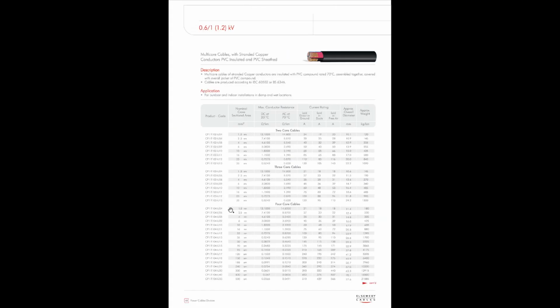So first we need a copper cable, 0.6/1.2 kilovolt. This one can withstand the 380 volt line-to-line voltage which we need. The second thing is how many cores we need. As the cable is supplying power to a three-phase load, a three-phase motor or a three-phase load with a neutral, we need three phases and a neutral. So we need a four-core cable. Okay, so let's zoom in.